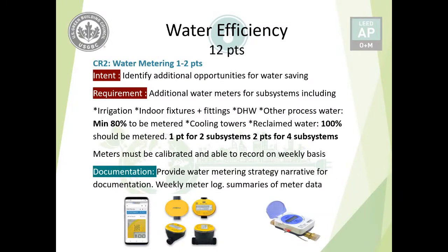However, for cooling tower, now if you submeter two subsystems, you'll gain 1 point, and if you put meters on four subsystems, you will gain 2 points.